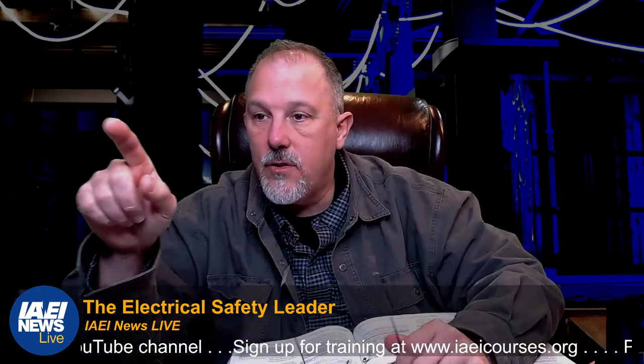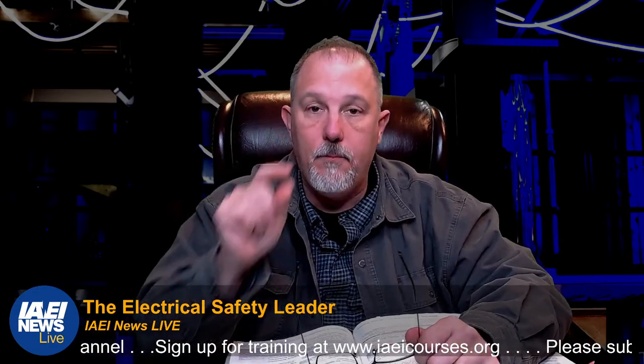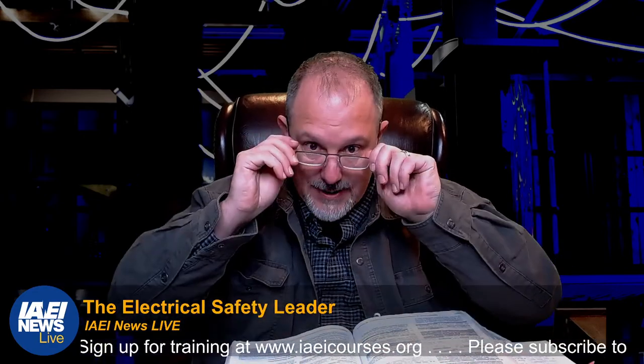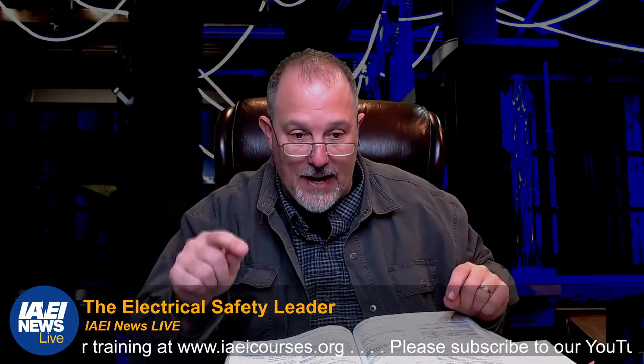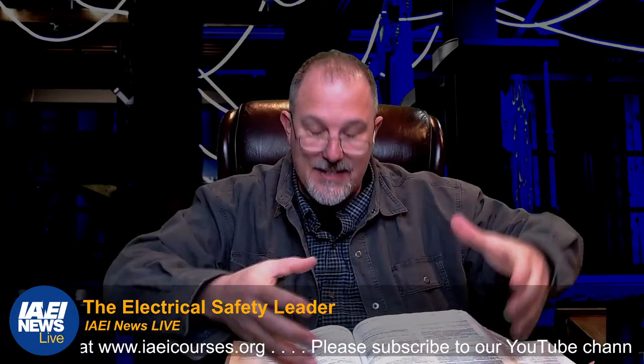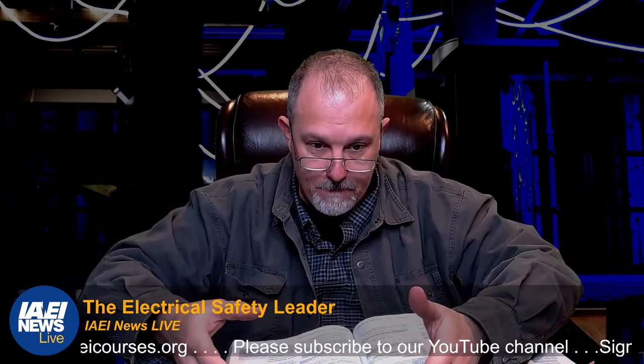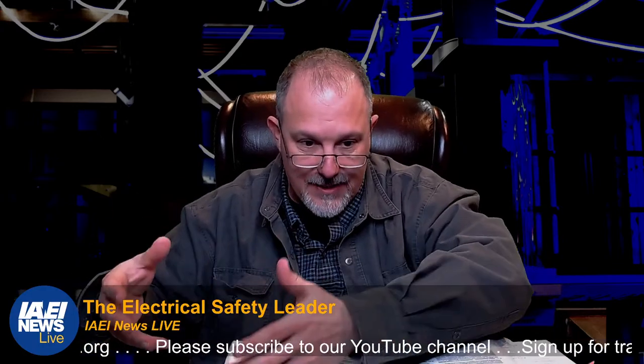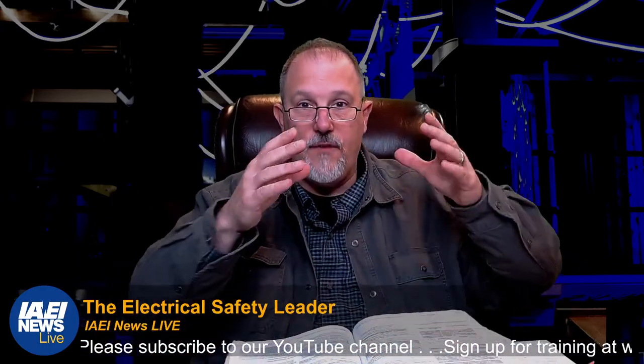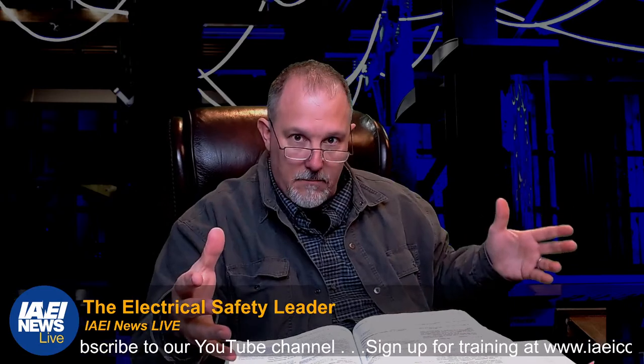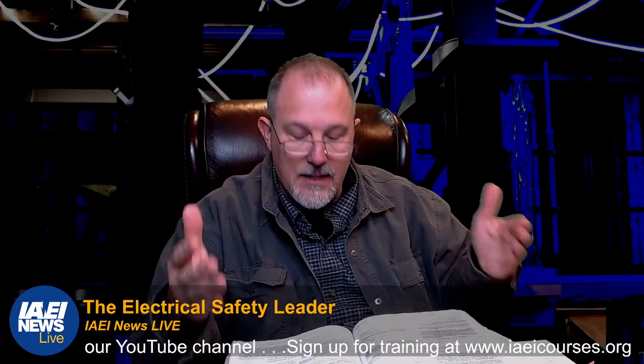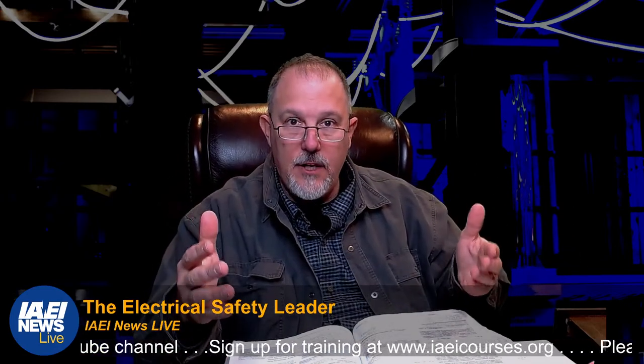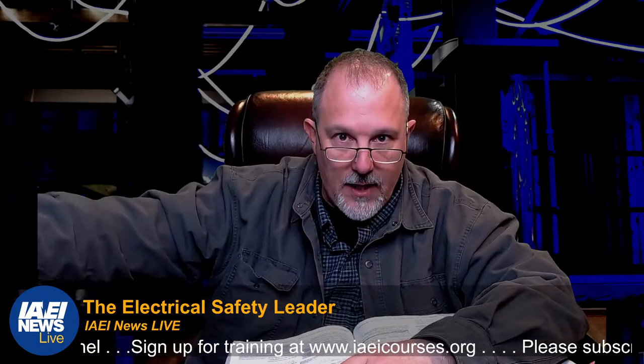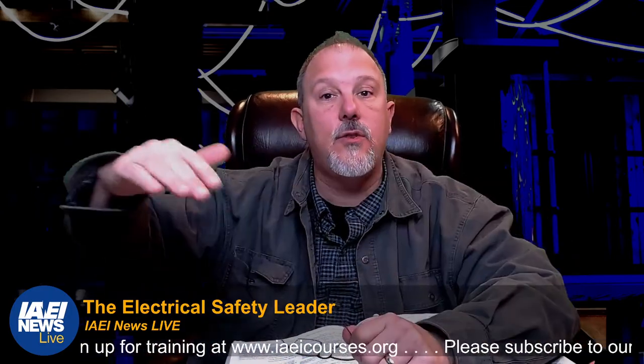To Mr. Hofkin and Robert's point, if they are listed to UL standard 9540, that's the standard for safety for energy storage systems and equipment. So if you have a system listed to UL 9540, you're following Article 706 - you're automatically into an energy storage system.